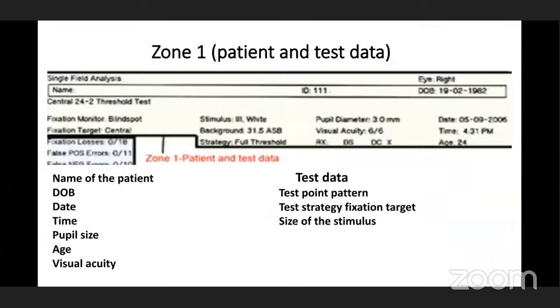In zone one, patient data includes name, date of birth, date, time, pupil size, age, and visual acuity. Age should be entered properly; otherwise it will not match with the normative data stored in the instrument. Pupil size should be normal but not too small — if it is less than 2 mm, there will be edge scotomas.